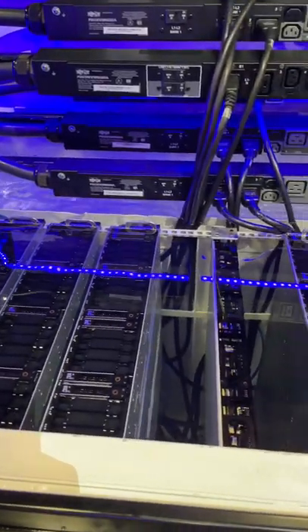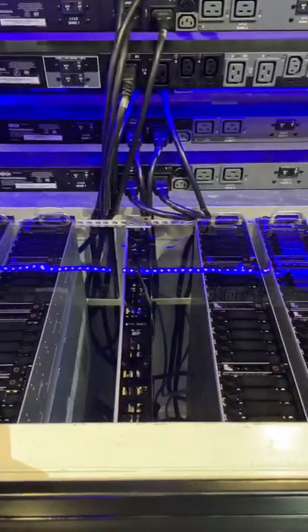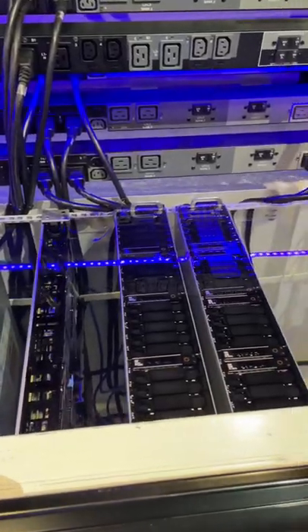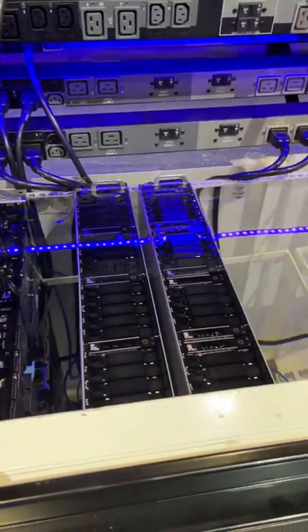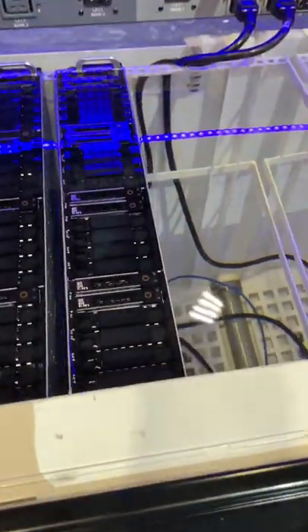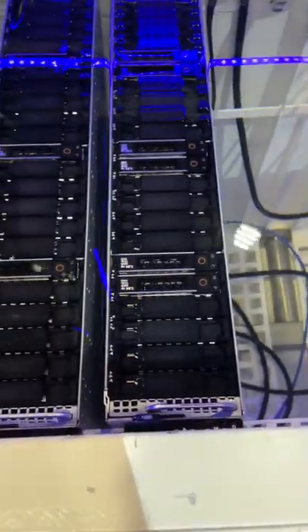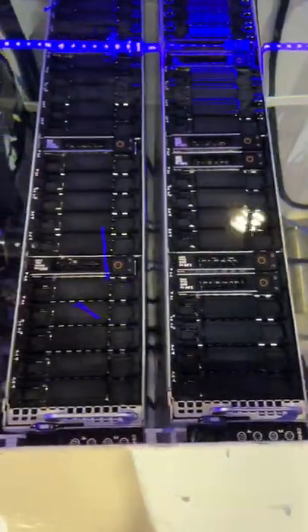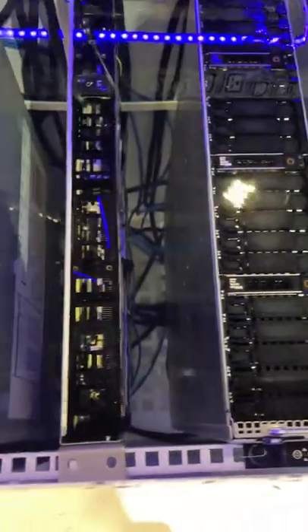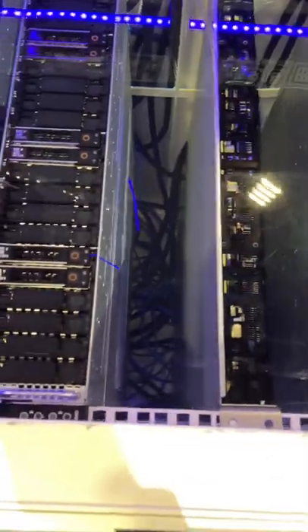Allows you to take off the shelf servers and run them in immersion. We deliver a cooler fluid in the bottom of the tank and use natural heat convection to rise the heat out of the servers to the top of the tank and evacuate it back out over a weir wall.